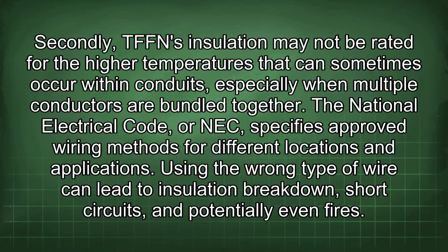Secondly, TFFN's insulation may not be rated for the higher temperatures that can sometimes occur within conduits, especially when multiple conductors are bundled together. The National Electrical Code, or NEC, specifies approved wiring methods for different locations and applications. Using the wrong type of wire can lead to insulation breakdown, short circuits, and potentially even fires.